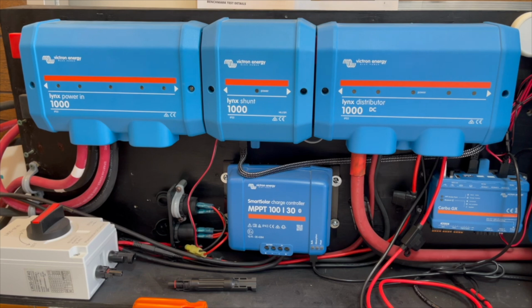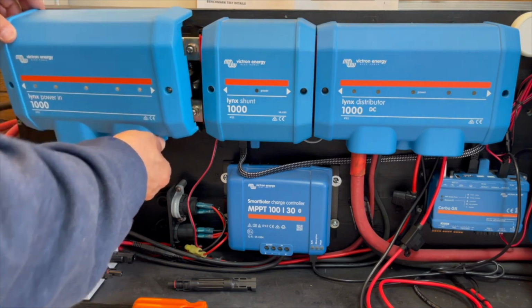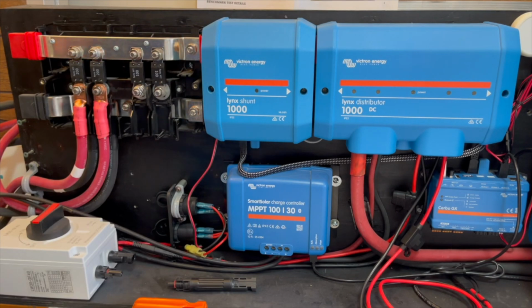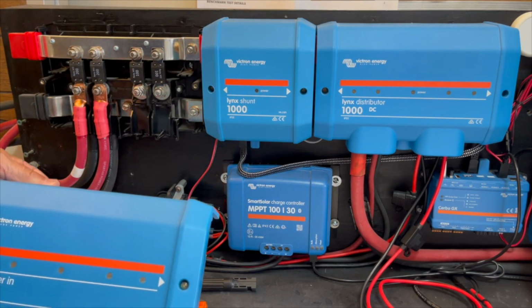The Lynx Power In, which is the far left unit, comes with no fuses or fuse mounting. I just get some M8 nuts and bolts, and there are 4 lines in there, so I have 4 fuses. I size the fuse to match the capacity of the battery, whatever its limit is for charging and discharging.